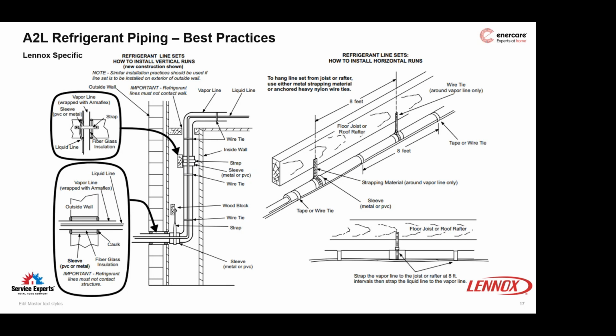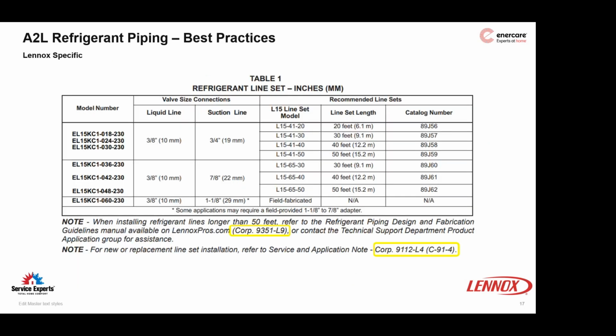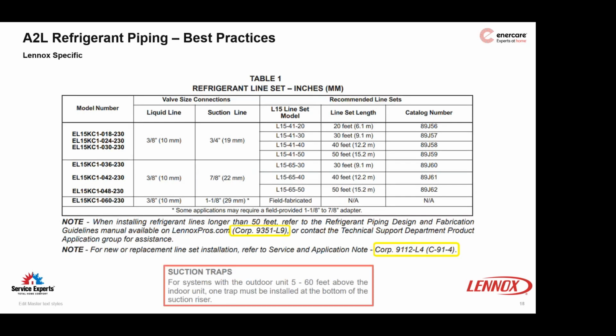It actually states it on the last page there, Jim. If you go back a page, it'll say exactly where to put the trap, at the bottom. I think it was the last page. There it is, right there. One trap must be installed at the bottom of the suction riser, right at the bottom of your coil.